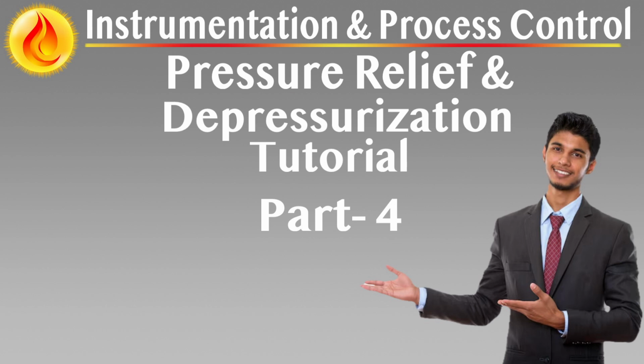Keep in mind that choked flow can occur at velocities below Mach 1.0, particularly at elbows, T's, and restrictions. Add an extra 10% back pressure margin above the recommended valve limits when approaching choked flow to ensure safety and stability. Vibration and mechanical loads.